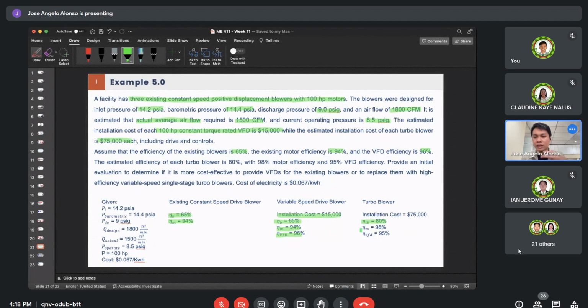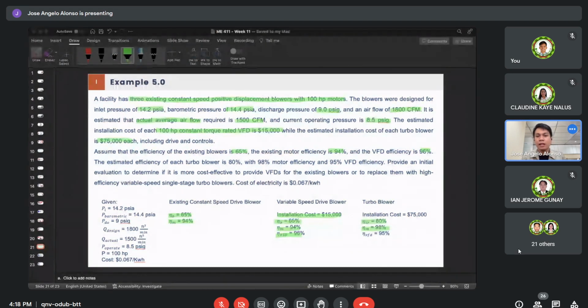The motor also has its own efficiency, that is 98%, relatively higher than the existing motor efficiency. And the VFD of our turbo blower has its own efficiency of 95%. So the turbo blower package is really the whole package—it already has the blower, the motor, and the VFD. That's why it's quite expensive since everything gets replaced. The installation cost is around $75,000.